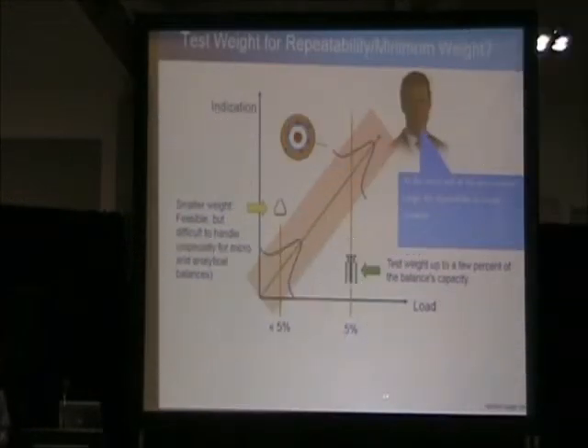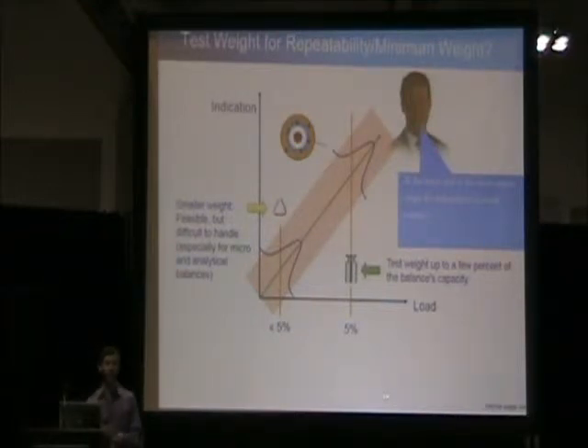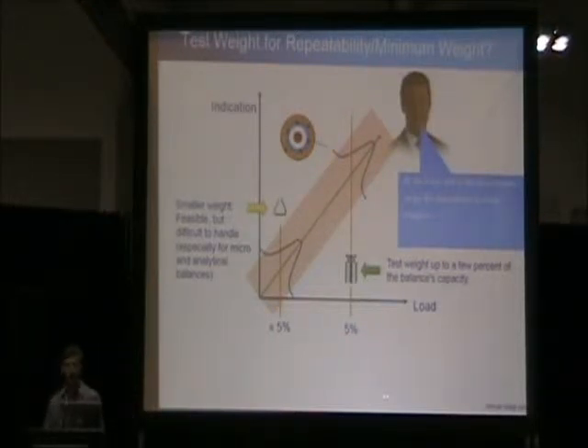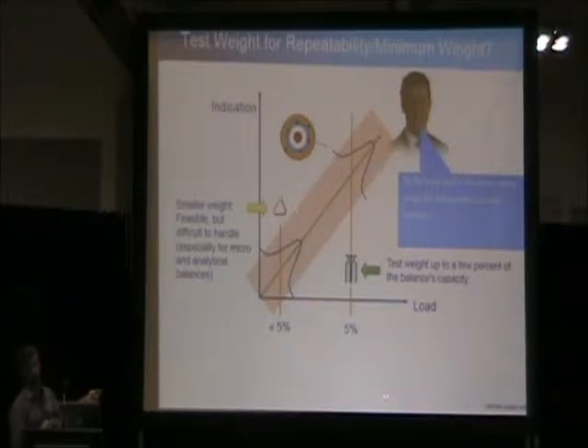So with the new USP requirements for Chapter 41, they actually specify the test weight that you should use for the repeatability test. Now, it was common practice prior to use a wire weight to perform this test on an analytical or a microbalance.